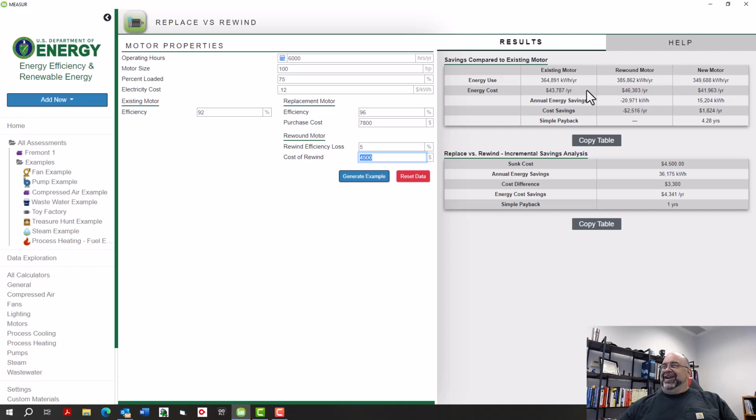But in any case, you can see here, the original one should have been about 43,780 or 43,800. After the repair, the annual running cost is going to be about 46. You notice that a repair versus replace decision actually involves the energy. So that makes that repair versus replace, which is a maintenance decision, not an energy decision, right? Would be to do that.